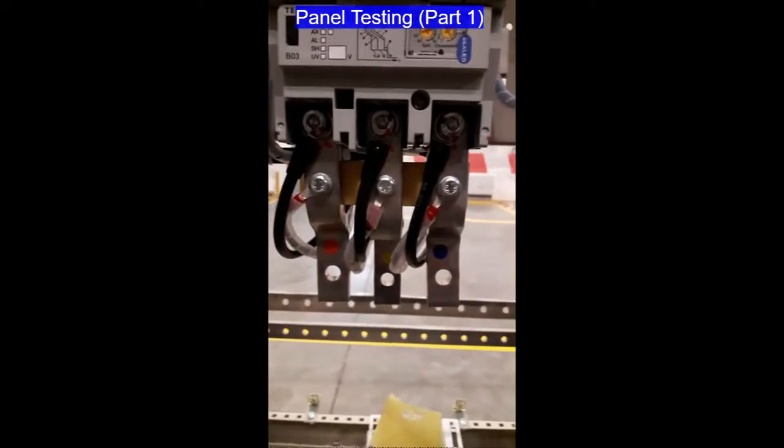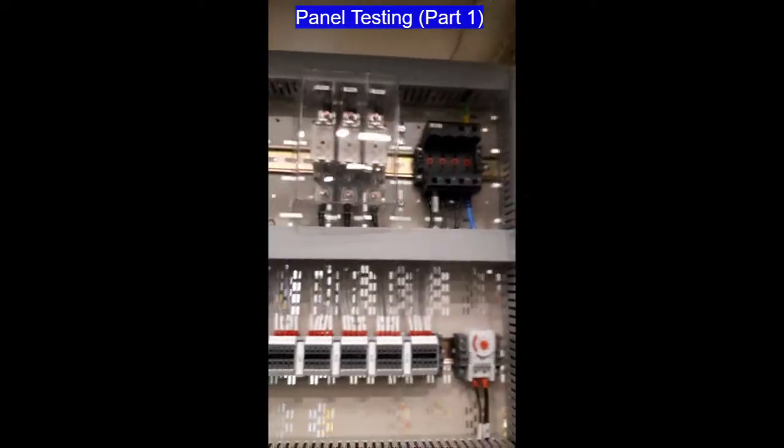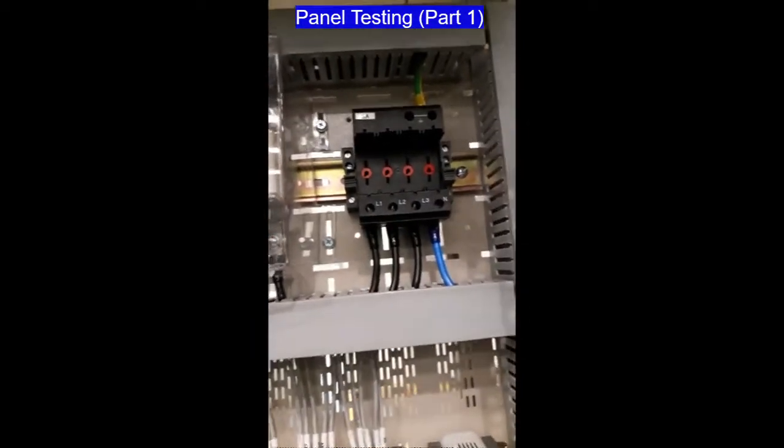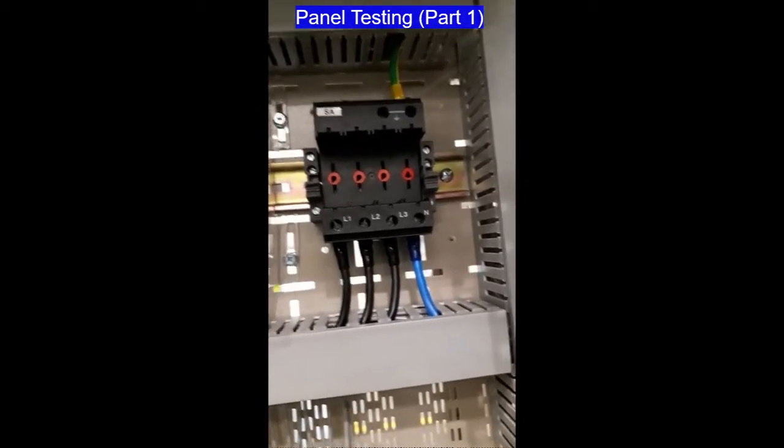We also have an extension bus bar for the incoming cable and a surge arrester. The surge arrester has been removed because we are going to perform the megger test — the insulation test.